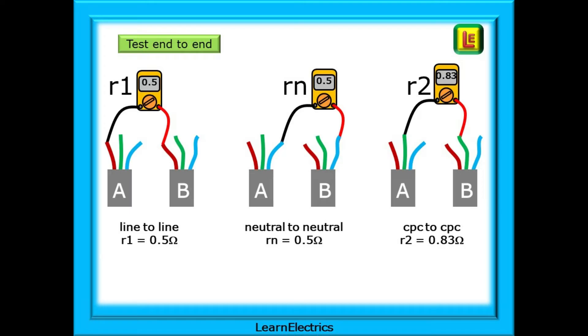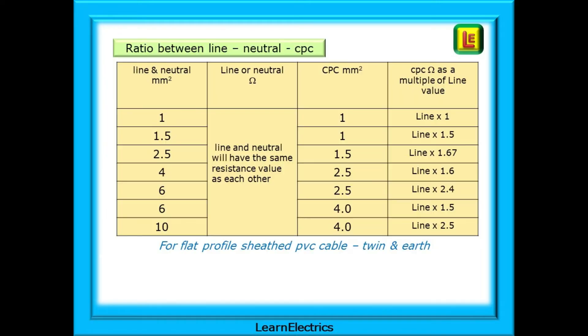This table shows how we get the ratios of line to CPC resistances for different size twin and earth cable. Find the twin and earth that you are testing, and the rightmost column gives the multiplication factor to use. Whatever the line reading is, multiply it by this factor to find the expected CPC value.